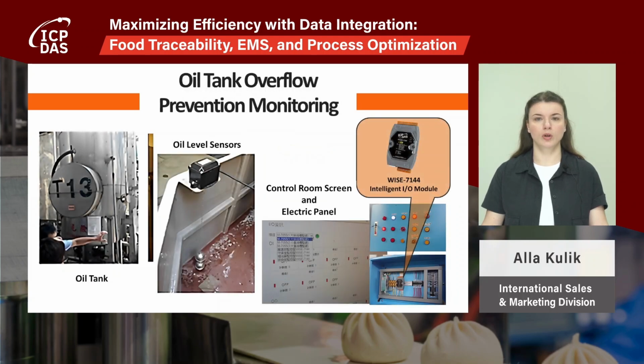To monitor oil tank levels, the factory installed sensors that transmitted data by Ethernet to the WISE-7144 I/O module. This information was then relayed to the SCADA system, enabling operators to track oil levels in real time. The system helped prevent overflows, ensured efficient oil usage, and was built to comply with regulations.